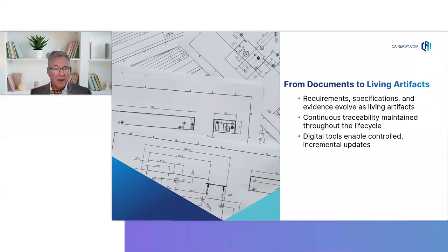Iteration requires a fundamental mindset change, especially around documentation. In an iterative model, requirements, specifications, and verification evidence are living artifacts, not static deliverables. They evolve as design matures and understanding improves. That doesn't mean losing control. It means maintaining continuous traceability rather than freezing documents prematurely.